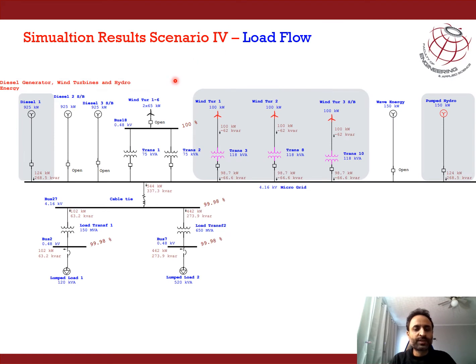Scenario 4 consists of a case similar to scenario 3. However, the wave energy generation has now been replaced by hydro energy. So you can see that the breaker for the wave energy has been opened and the breaker for pump hydro has been closed. So the total active power generation is now from the wind turbines as well as from the pump hydro. Active power from the diesel generator has reduced significantly, and the generator and the pump hydro are sharing the reactive power requirement of the wind turbines and the load. The voltage at the load bus is within the limits, and we were able to successfully get the results for load flow for this scenario also.